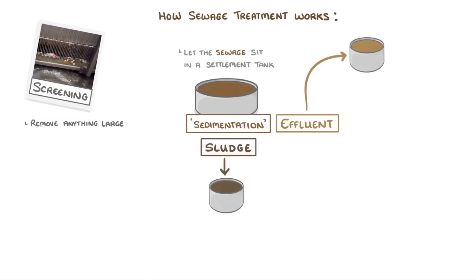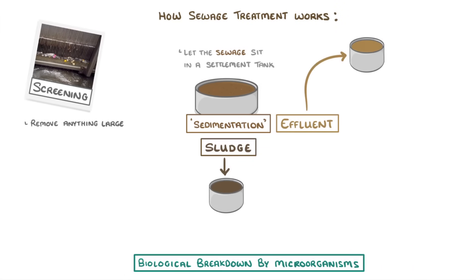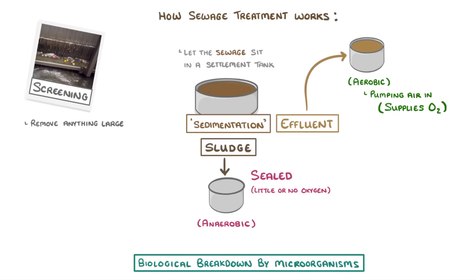The final stage is to break down all of the organic matter, and for that we rely on biological breakdown by microorganisms. The key difference between the two tanks is that the effluent is under aerobic conditions while the sludge is under anaerobic conditions. We can achieve this by pumping air into the effluent tank, which supplies oxygen, but keeping the sludge tank sealed so that there's little or no oxygen.